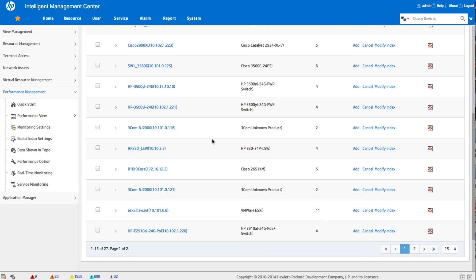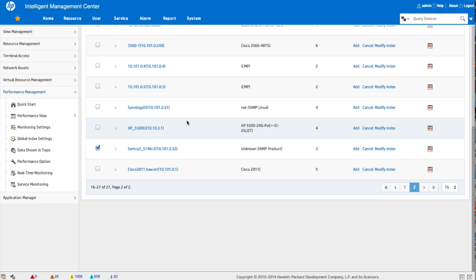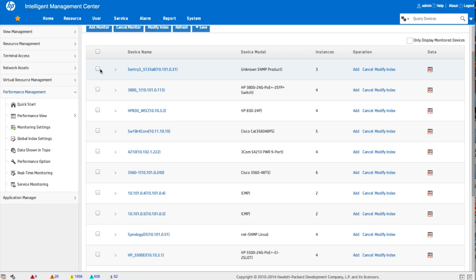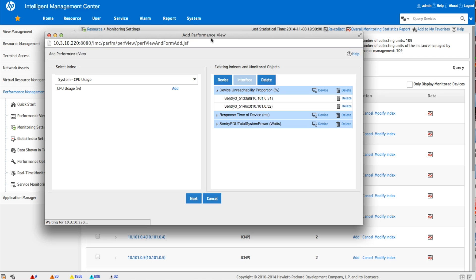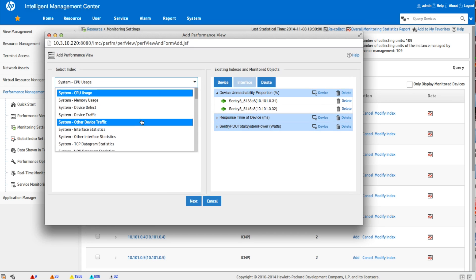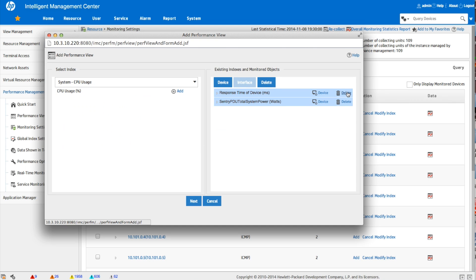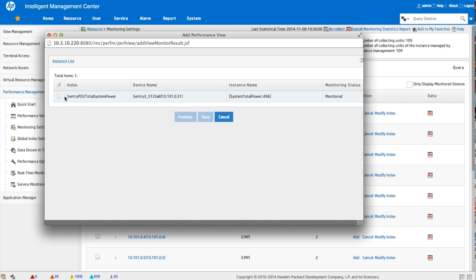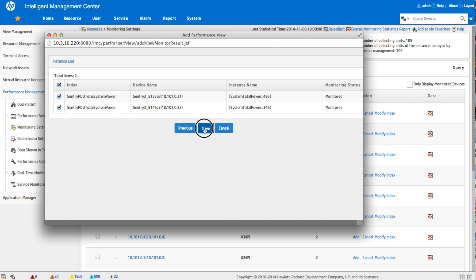Go down to the bottom. The boxes we're looking for are not on this page, so we'll go to page two. There's also some filtering that you could have done to get here as well, but we'll just do this the easiest way. So we'll click Sentry, click Sentry, there we go. And we're going to save this as a new view. So now I'm going to be creating a performance view. So just because you're tracking the information doesn't mean you have a place to go see it yet. It'll be there in the database. So if you wanted to do other tracks, you could go in here and select a specific index. But for my case, I'm just going to delete out everything except for that total power. I want to create a custom view where I can see the power that's being used. There we go. Got both of them. We're going to click save. Again, a descriptive name. So the Sentry PDU, total system power. Who do I want to have access to it? And the description is tracking power usage on Sentry, on Server Technologies, Sentry PDU, through SNMP. There we go. Click OK.